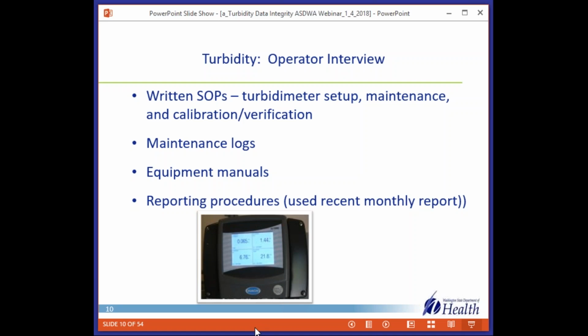From the beginning, we started with an operator interview, and we wanted to look at written standard operating procedures, or SOPs. We looked at, of course, turbidity setup, maintenance and calibration verification procedures. We asked for and looked at maintenance logs, and frequently asked a specific question and then looked for where that's documented. We wanted to physically touch equipment manuals, and then we looked at reporting procedures. And we used the monthly report that the utilities sent to us. We'd maybe pick a date and find out where those different values came from.